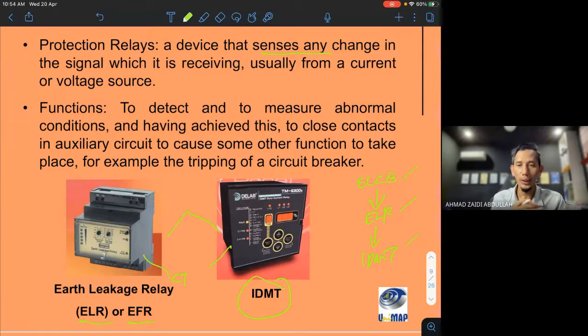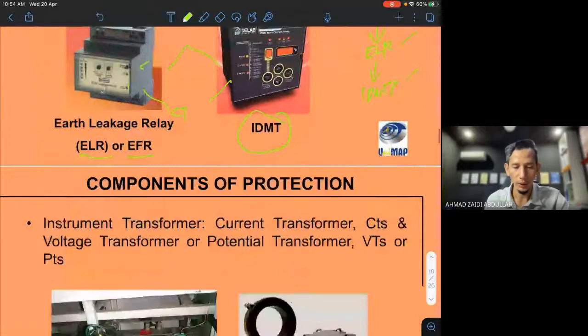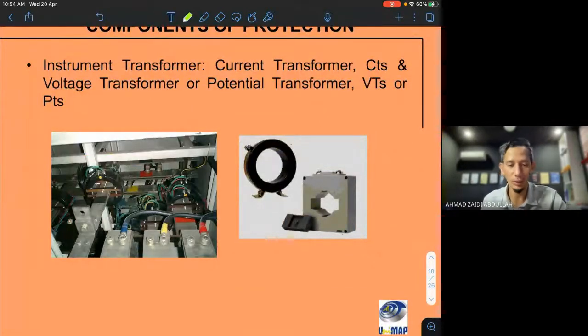So when you are dealing with the relay, make sure you also include the CT or VT, because this relay can only perform with very low current or low voltage. Kan, let's say your project is 100 amp, as I mentioned earlier. But the ELR can only receive a very small current, so you need to step down the current first using a current transformer.